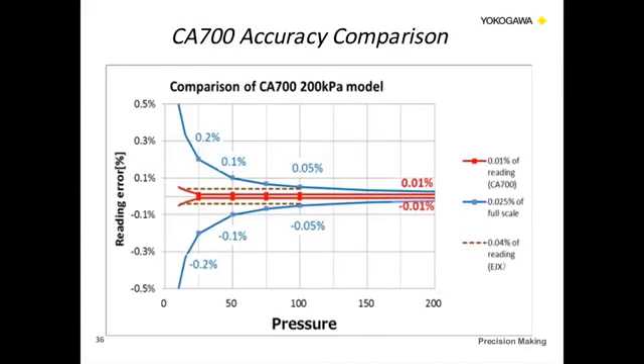So here is an accuracy comparison. The blue line that you see there is what you will typically find in most competitive pressure calibrators on the market today. That's typically about 0.025% of full scale. The scale here is 200 kPa, so roughly 29 PSI. And the red line that you see there is 0.01% of reading. That is the accuracy of the CA700. And then there's a dotted line there that is an EJX transmitter for comparison purposes as well.